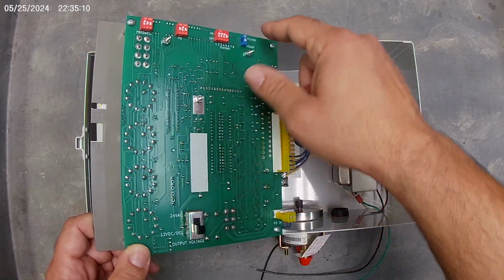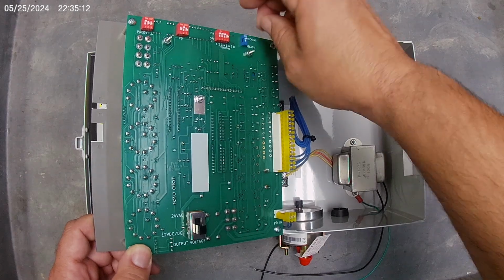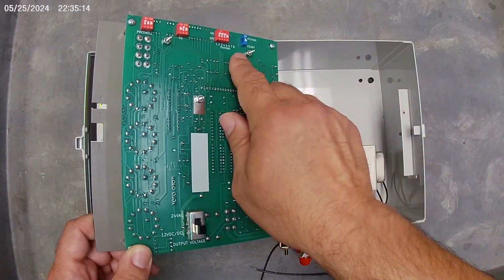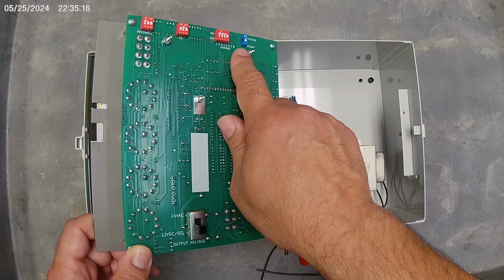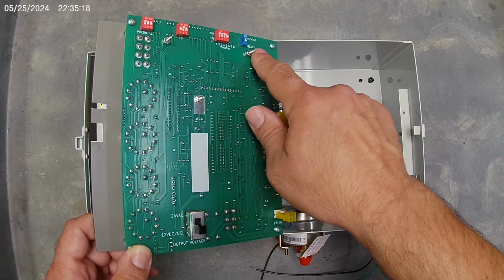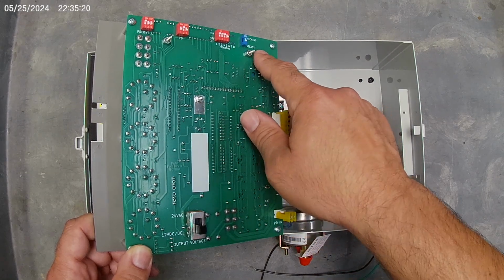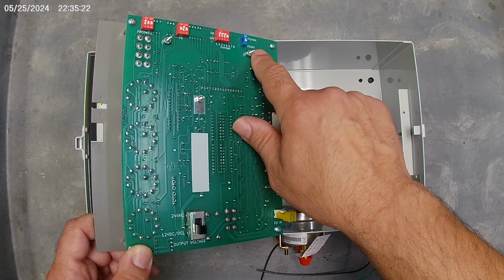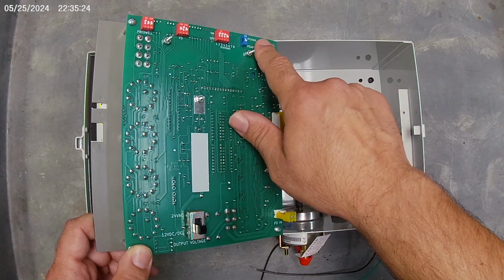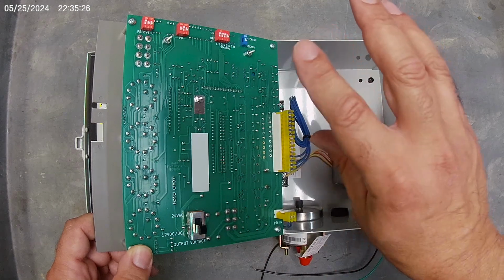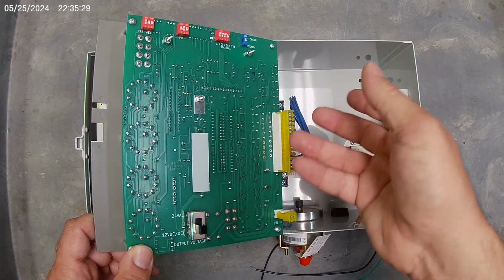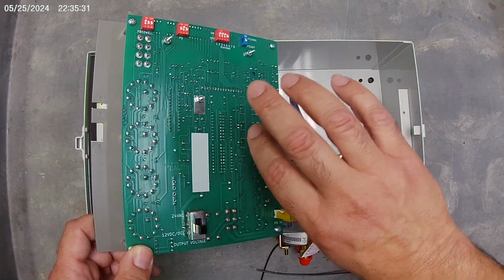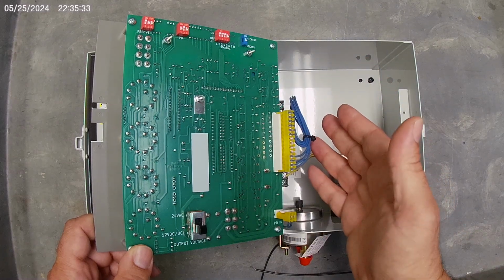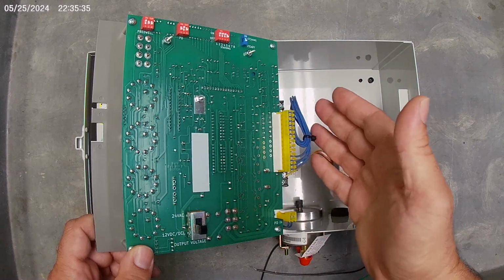The last switch is latching or steady, and again, that is determined by which type of solenoids you have. More often than not, you'll have steady or regular solenoids that require continuous power to stay on. Latching will send a pulse one direction to turn the solenoid on and a pulse the other direction to shut it off. This is typically used in battery or solar powered systems.